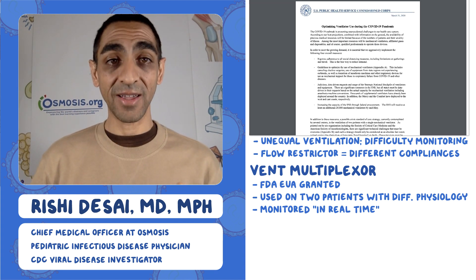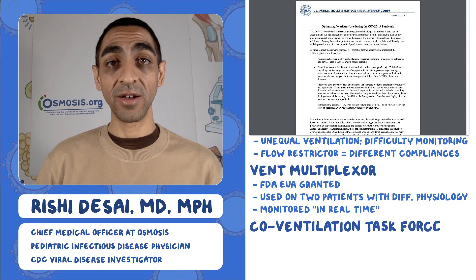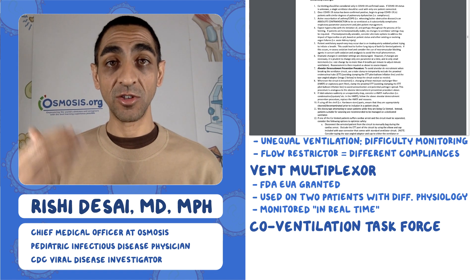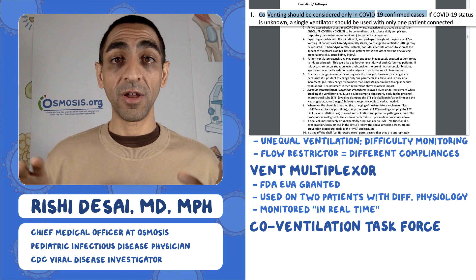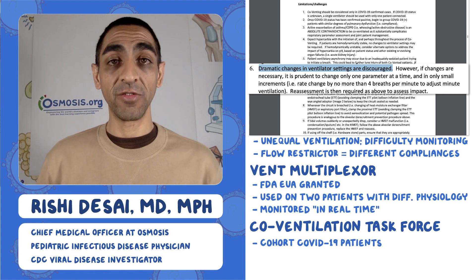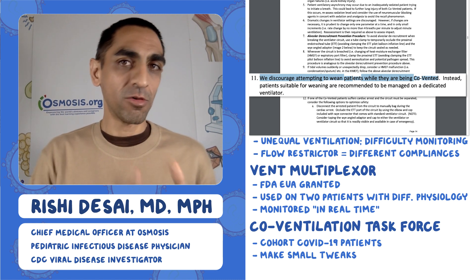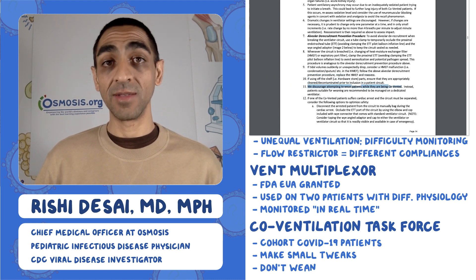This brings me to a final document from the U.S. Public Health Service Commissioned Corps, which has a task force on how to use split ventilators. If you're at a hospital considering this, I strongly suggest reading it carefully. A few key points: make sure all patients on the shared vent have the same disease — in this case, both should have COVID-19 — to avoid spreading infections. Don't make dramatic changes on the vent in a shared setting; make changes very subtly. If you're trying to wean someone off the vent, put them on their own vent — those sharing should be more stable and static in their needs.